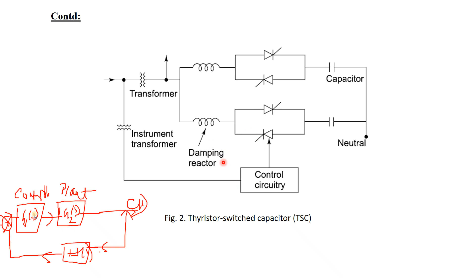It consists of a thyristor switched capacitor, which is split into a number of units of equal ratings to achieve stepwise control. As such, they are applied as a discretely variable reactive power source, where this type of control is deemed adequate. All switching takes place when the voltage across the thyristor valve is 0, thus providing almost transient-free switching. That means when the switching operation is performed, it takes place when the voltage across the thyristor valve is 0. So under zero voltage condition only, the thyristor switching takes place.